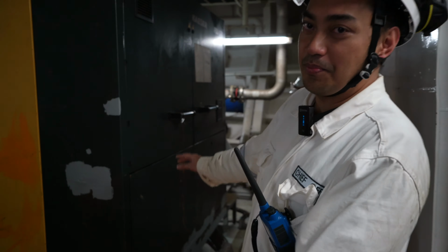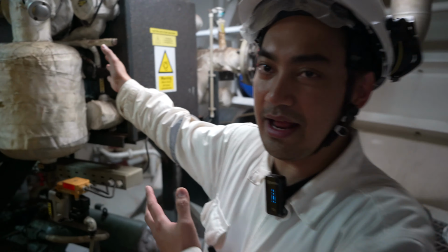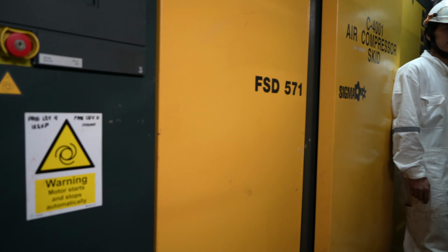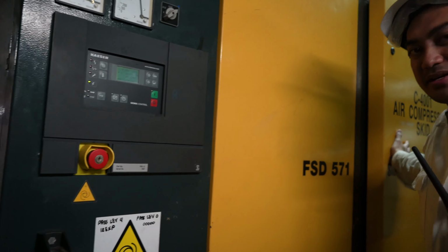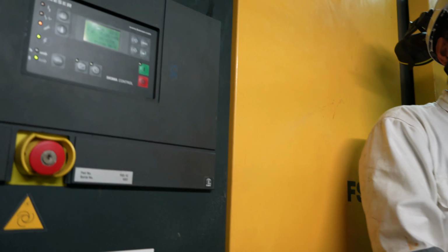This is the air compressor. And this is the air dryer. The air compressor is for the generation of air, sucking the air through an air intake, and then this is processed before it is thrown to the air dryer, which lessens the dew point as much as it could before going directly to the PSA, because any permission of water to the adsorbers makes damages that are irreversible. Okay?